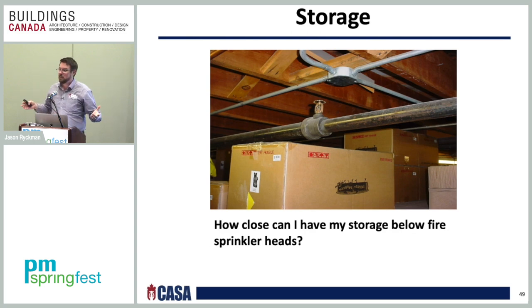Something I see all the time in buildings. Obviously, owners try to maintain and try to use as much space as possible in their buildings, right? And sometimes you guys go a little above and beyond what you should be going whenever it comes to storage. So how close can I be for my storage to my sprinkler head? The answer to your question is 18 inches. You have to maintain a minimum of 18 inches for any sprinkler head. Now, there are some exceptions where it has to be more than that. So if you have tire storage, it has to be 36 inches.